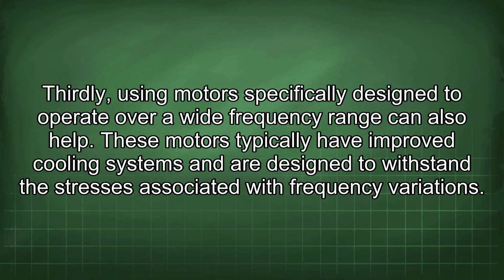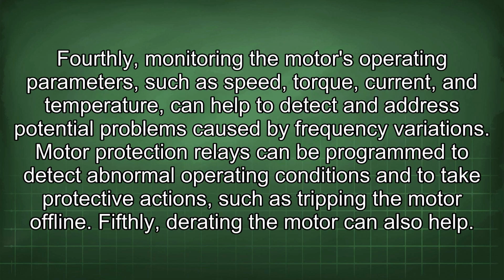Thirdly, using motors specifically designed to operate over a wide frequency range can also help. These motors typically have improved cooling systems and are designed to withstand the stresses associated with frequency variations. Fourthly, monitoring the motor's operating parameters such as speed, torque, current, and temperature can help to detect and address potential problems caused by frequency variations.